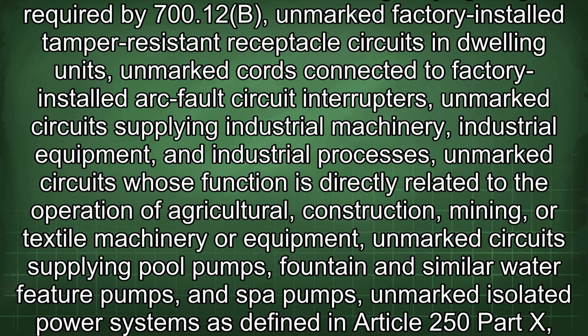There are exceptions for unmarked factory-installed branch circuits for emergency lighting as required by 700.12(B), unmarked factory-installed tamper-resistant receptacle circuits in dwelling units, unmarked cords connected to factory-installed arc fault circuit interrupters, unmarked circuits supplying industrial machinery, industrial equipment, and industrial processes, unmarked circuits whose function is directly related to the operation of agricultural, construction, mining, or textile machinery or equipment, unmarked circuits supplying pool pumps, fountain and similar water feature pumps, and spa pumps, and unmarked isolated power systems as defined in Article 250 Part X. Replacement of arc fault circuit interrupters is permitted without replacement of the marking.